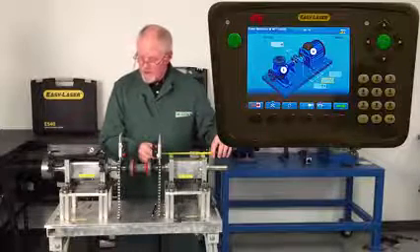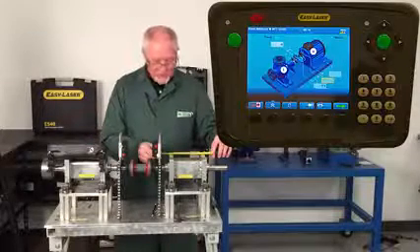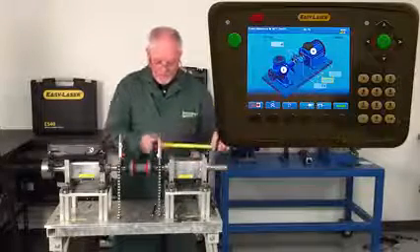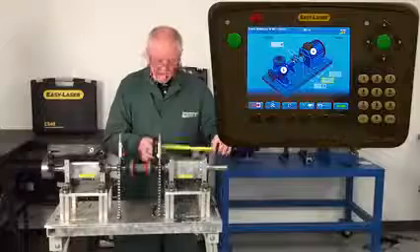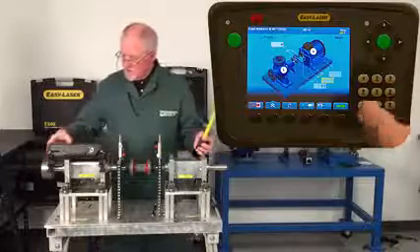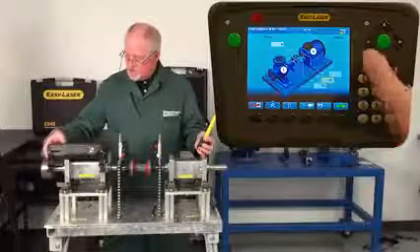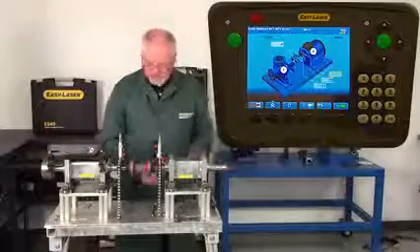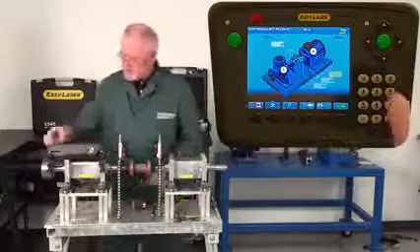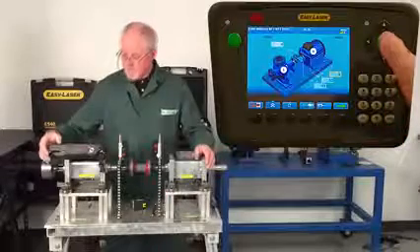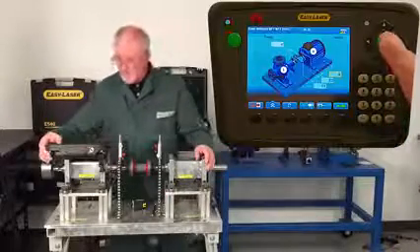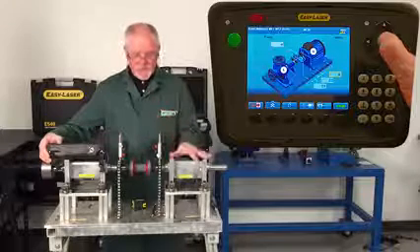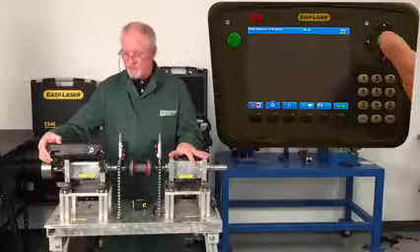Now it says M to MF1, which is movable foot one, movable machine foot one. And I've got two and a quarter, 2.2, enter. And the last measurement is the distance between the machine's feet, which is six inches. Now I have everything that I need in order for the machine to be able to take some readings and then calculate how much shim we're going to have to put underneath.